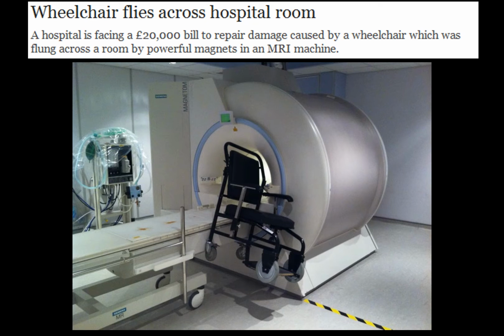The very strong static magnetic field associated with clinical MRI systems poses a serious safety risk with any ferromagnetic object, be it scissors or in this case a wheelchair, turning into a projectile due to the attractive force of the magnet. Fortunately, nobody was injured in this case, but this wheelchair would have been attracted to the magnet at around 30 miles per hour.